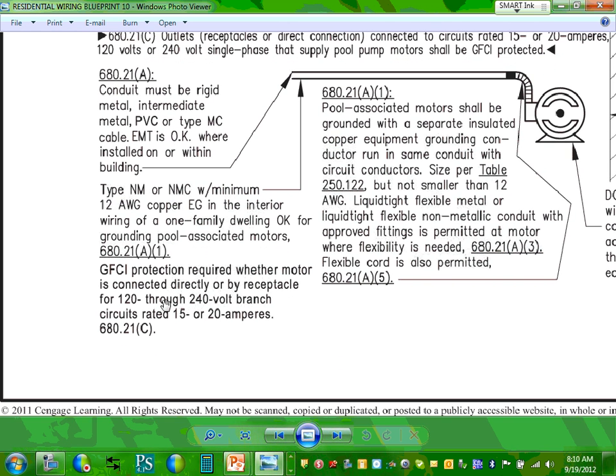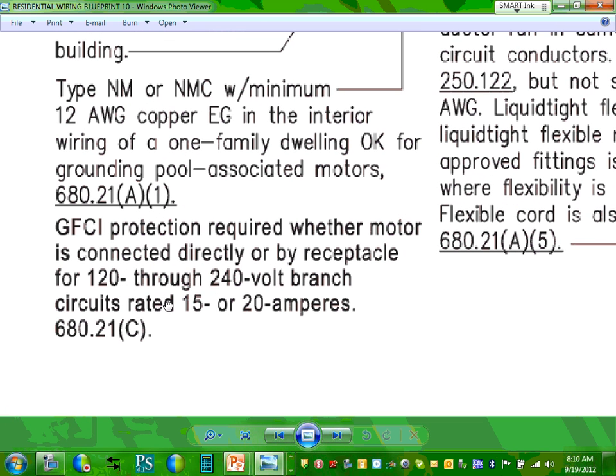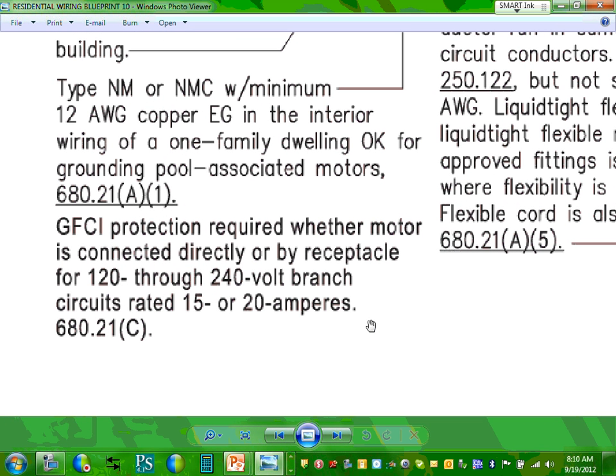If you have a pump, in your case, what's the voltage of the pump that we're running for our project? Anybody remember the voltage? 240. If you have a swimming pool pump that runs at 120 through 240, that will cover 120 and 240 voltages, single phase. And if the pump is powered with a 15 amp or 20 amp circuit, this pump has to be GFCI protected. Exactly what you guys are going to have. It's going to be a GFCI circuit breaker protecting it.